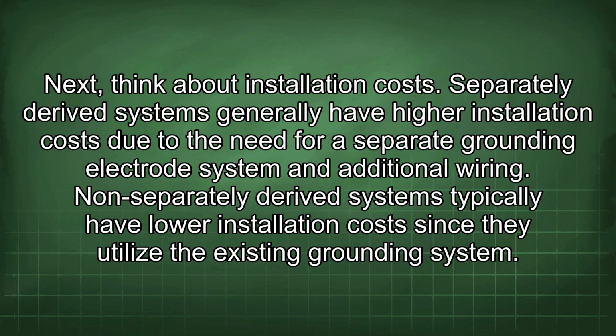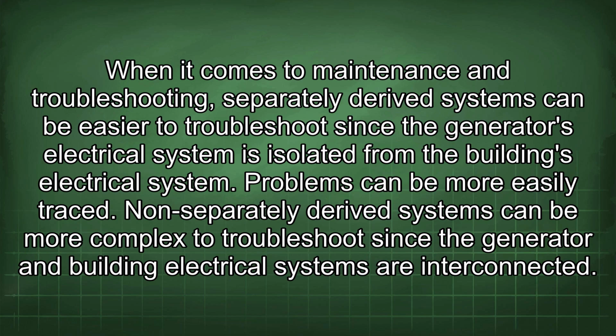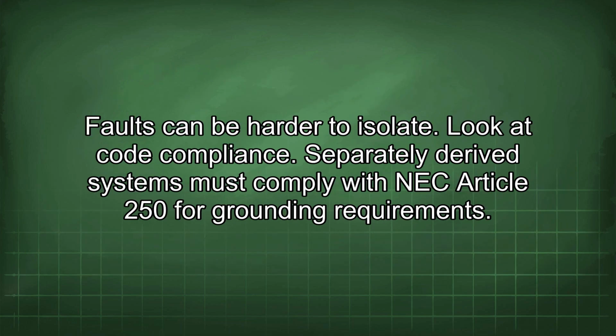Separately derived systems generally have higher installation costs due to the need for a separate grounding electrode system and additional wiring. Non-separately derived systems typically have lower installation costs since they utilize the existing grounding system. When it comes to maintenance and troubleshooting, separately derived systems can be easier to troubleshoot since the generator's electrical system is isolated from the building's electrical system. Problems can be more easily traced. Non-separately derived systems can be more complex to troubleshoot since the generator and building electrical systems are interconnected. Faults can be harder to isolate.